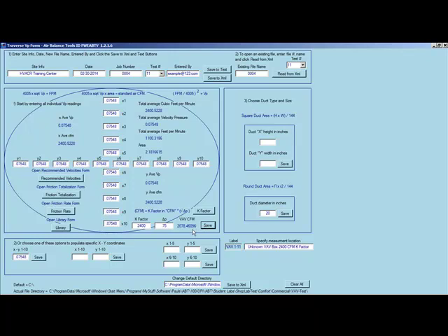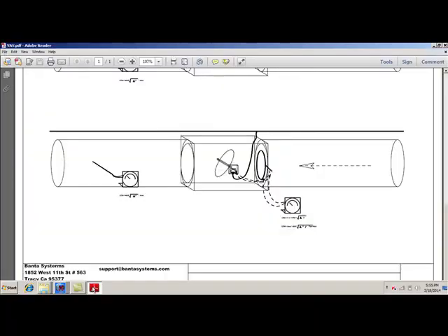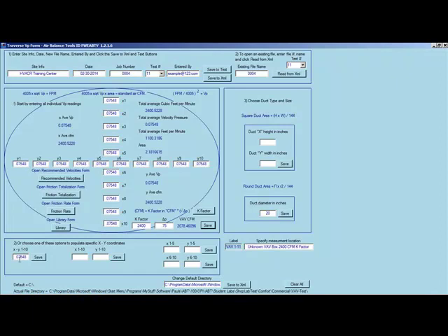That would give us a VAV CFM of 2078 CFM. Now what we should see on the outlet to match that 2078 CFM, we'll adjust the reading and see what it would be at 2078.